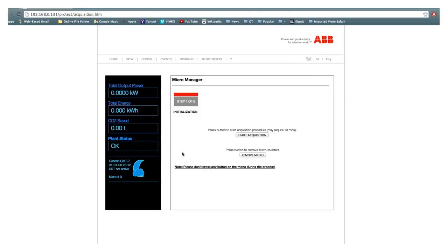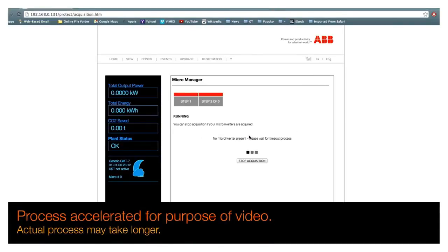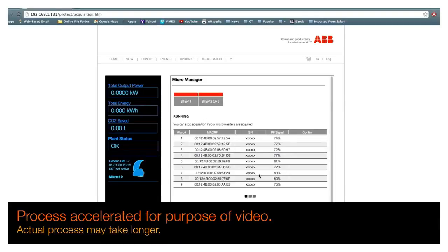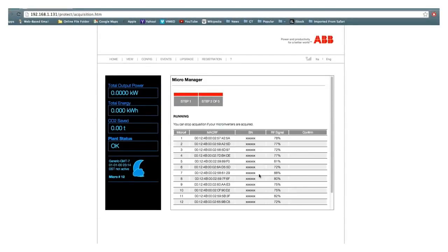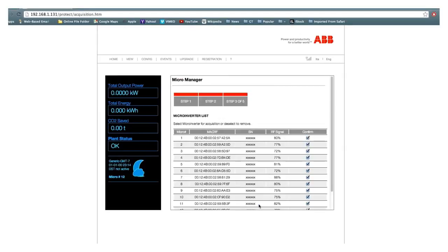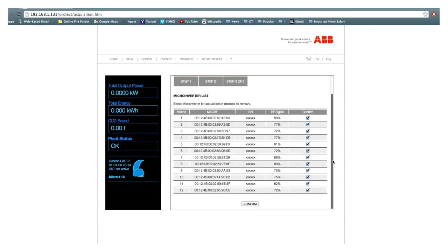To start the acquisition, click the Start Acquisition button. The micromanager will scan for available microinverters within range. This process may take up to 10 minutes. When you see the desired number of inverters acquired, press the Stop Acquisition button. Note there are 12 inverters per box. The micromanager will display the MAC address and serial number of each inverter found. Compare these to the MAC addresses and serial numbers of the microinverters installed on the site. If there are undesired microinverters found, uncheck the box on the same line of the undesired microinverter. Once all microinverters have been acquired with a max of 30 per CDD, click the Confirm button.